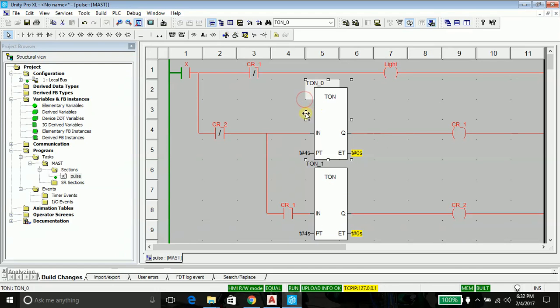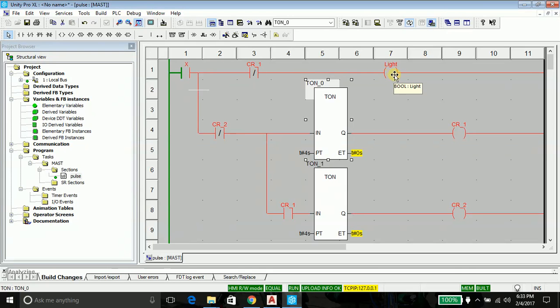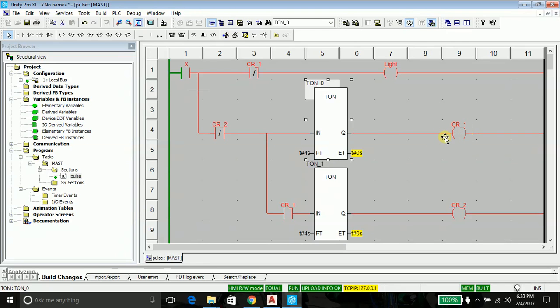Let's discuss: when we have current coming and when we press the button, what will happen? The current will go simultaneously through this branch and this branch. When it is going through this branch, it will light up the light, as it will pass through this contact—it is a normally closed contact—so it will light up the light. And when it goes through this branch also, it will pass this contact and it will activate this timer.